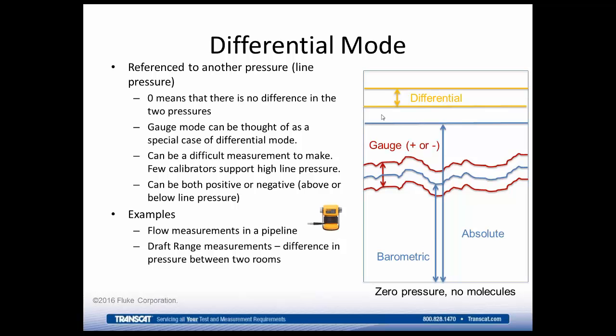Another example of differential mode is what we call a draft range measurement, and that's where you're looking at the difference in pressure between two rooms. A key example of that would be rooms that have a positive pressure, such as the operating room in a hospital. They're specifically designed so that when you open the door, none of the germs from outside of the operating room get sucked into the operating room, but instead the other way happens: the air from inside the operating room moves out towards the outside. And you do that by having a higher pressure inside of the operating room versus the outside room. So you're interested in seeing what the difference is between those two rooms, and that in essence is a differential pressure measurement. We refer to it as draft range because it's a pressure that can be generated just by the draft of air.